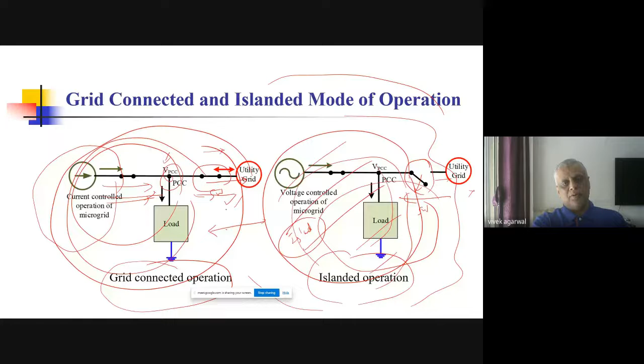And the rest of the inverter systems or converters just work in current control mode, and just keep feeding power into the PCC. Okay, here there's no problem. If there is any deficit, you can take from the grid. If there is any surplus, you can give it to the grid. So this is a very nice situation. Control is easy and flexible, and you can really do a lot of things.